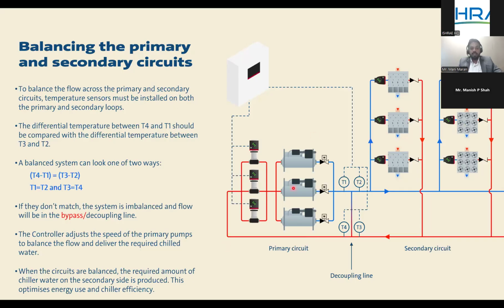The primary flow is 100 gallons per minute and the secondary flow is 200 gallons per minute. The excess 100 gallons per minute will go through this decoupler line, and it increases the T2. It's supposed to be 20, but it will increase to 21. Now, by understanding the logic of T4 minus T1 and T3 minus T2, when there is a change in the load, that signal will be fed to your CPM or BMS or PLC, and that will send a signal back to the pump to increase its speed.